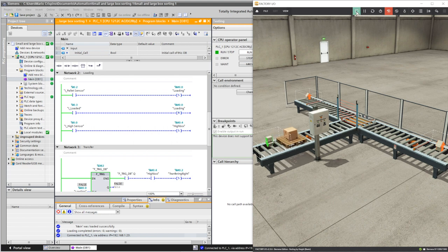Okay, pallets are traveling down the entry conveyor and entering the small loader conveyor. The pallet is loaded and the yellow bed and chains rise and tries to move the pallet to the right. But two things appear to be wrong with the program. Firstly, the right conveyor is not running, creating friction between the pallet and the right conveyor. So the pallet is struggling to move off the loader.